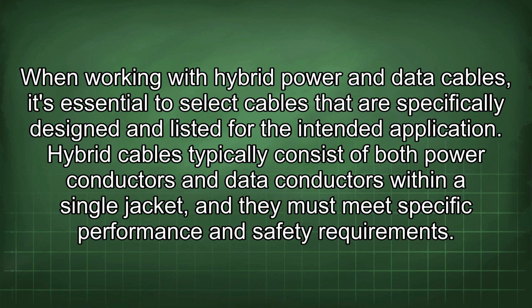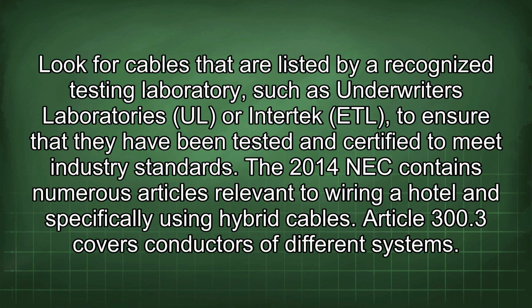When working with hybrid power and data cables, it's essential to select cables that are specifically designed and listed for the intended application. Hybrid cables typically consist of both power conductors and data conductors within a single jacket, and they must meet specific performance and safety requirements. Look for cables that are listed by a recognized testing laboratory, such as Underwriters Laboratories (UL) or Intertek (ETL), to ensure that they have been tested and certified to meet industry standards. The 2014 NEC contains numerous articles relevant to wiring a hotel and specifically using hybrid cables.